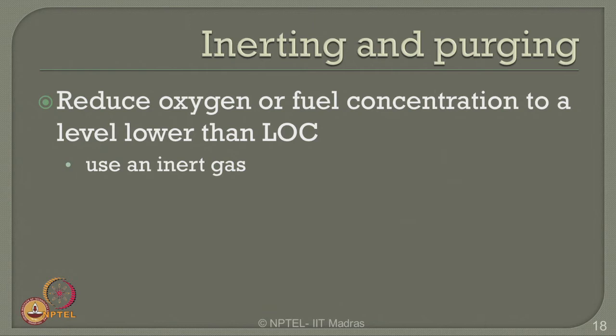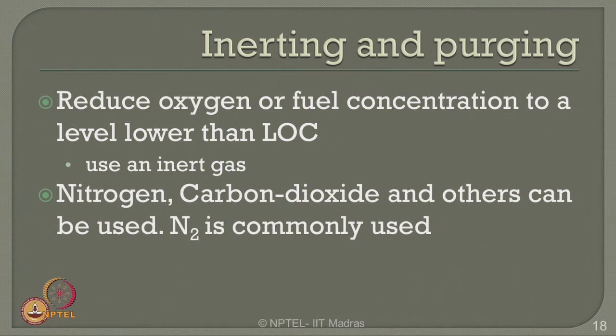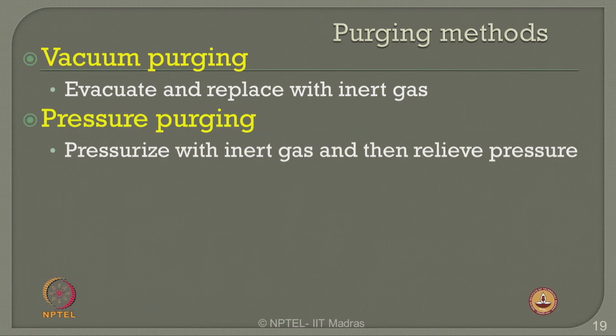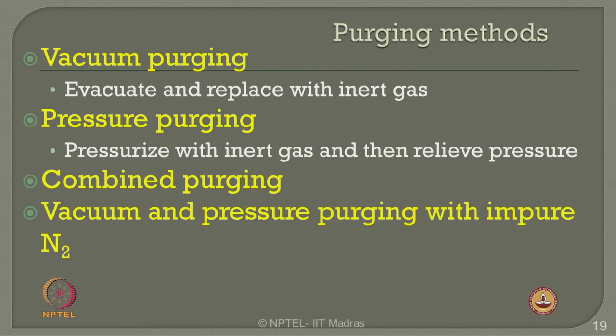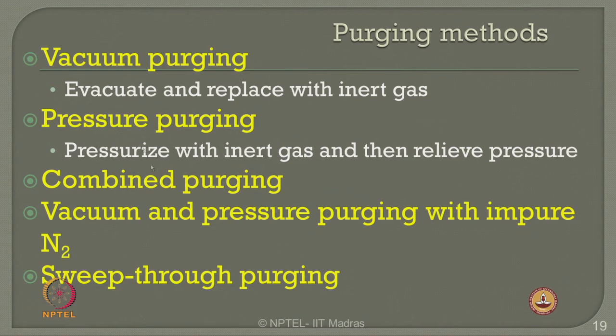Inerting and purging is a process by which oxygen content or fuel concentration is reduced to a level lower than the limiting oxygen concentration. To do this, one generally uses an inert gas. Nitrogen, carbon dioxide, and others can be commonly used, but nitrogen is most popularly used. The commonly used control point is 4 percent below the limiting oxygen concentration. Different purging methods include vacuum purging, pressure purging, combined vacuum and pressure purging with impure nitrogen, and sweep-through purging.